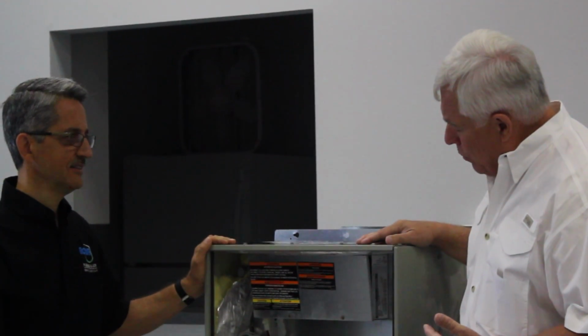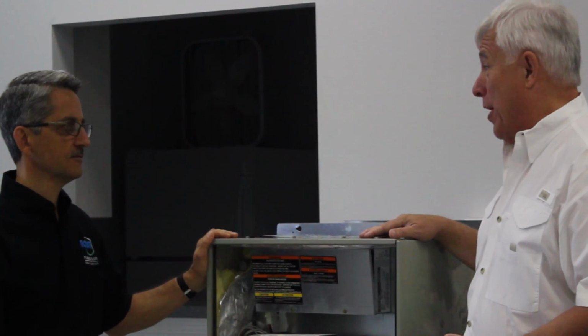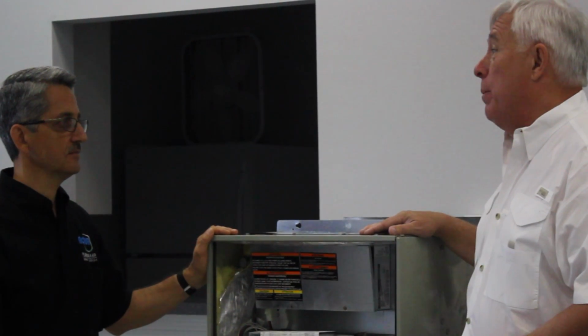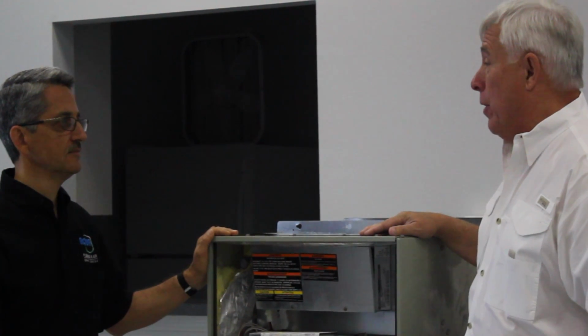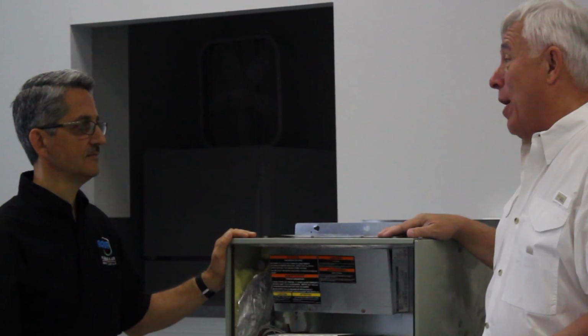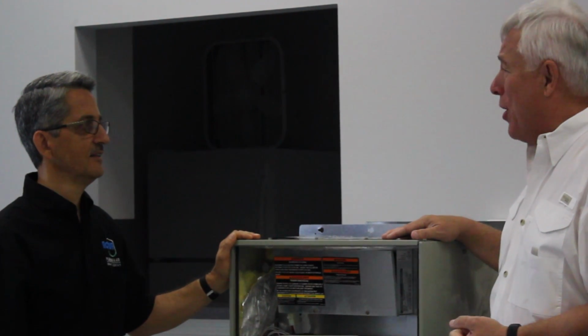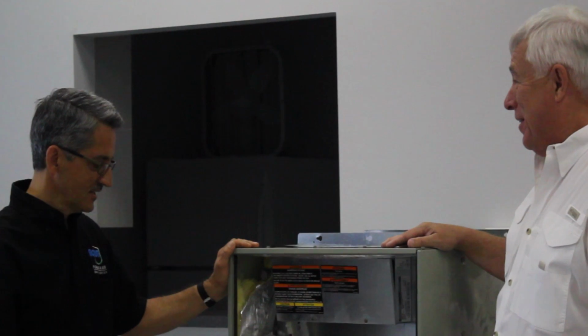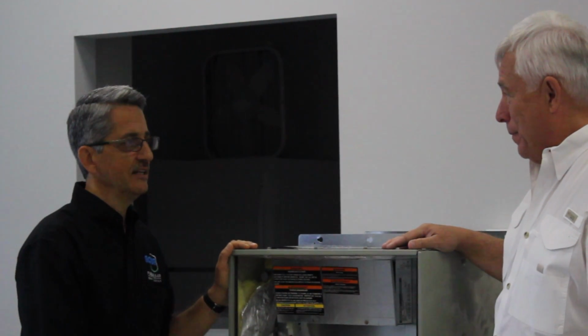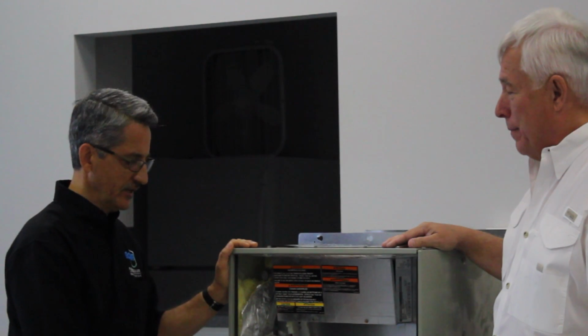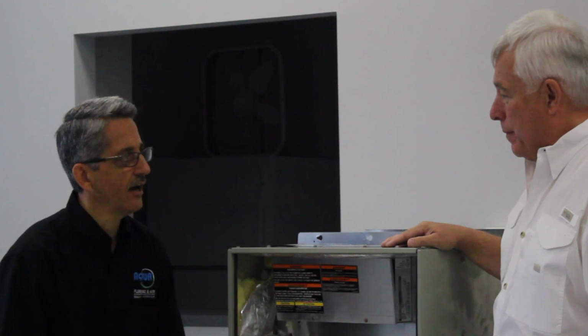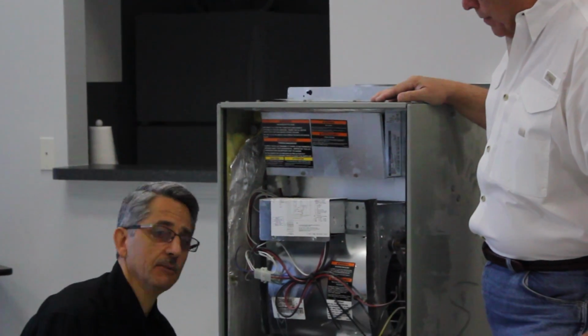I know that really an air conditioner is a big dehumidifier. When we lower the temperature through the evaporator, we're taking water out of the air. Where does that water go, and does it cause problems for the average homeowner? The coil absorbs the heat and in doing so also takes moisture out of the air. That moisture drops into a drain pan at the very bottom, and there's a pipe connected to that pan that runs to the outdoors, so the water taken out of your home through the air handler gets discharged outside.